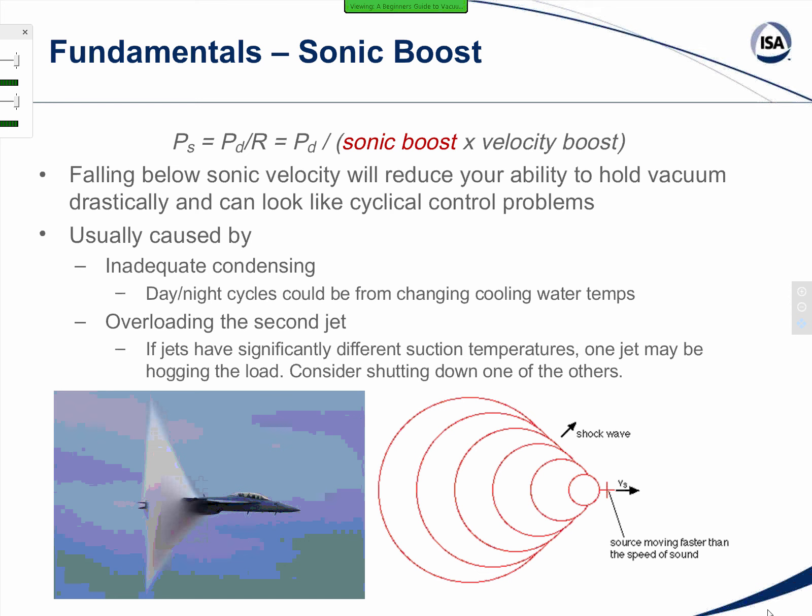Generally that's why when you hear a vacuum system that's working well, the jet ejectors are going to be roaring pretty loudly. This is them being up at that sonic boost range. Falling below sonic boost is going to greatly reduce that R factor and it's going to reduce your potential suction pressure. Things to check to see whether or not you're in that sonic boost range are to look at your condensing, make sure that you have adequate condensing, and check to see if maybe one of your jets is overloaded if you have a series of them or parallel ones in place. One jet in parallel with another might be hogging a lot of the load, and so your second jet is out of that sonic boost range. You can consider turning it off completely and putting that extra load on the heavy hitter at the lower ranges that you need.